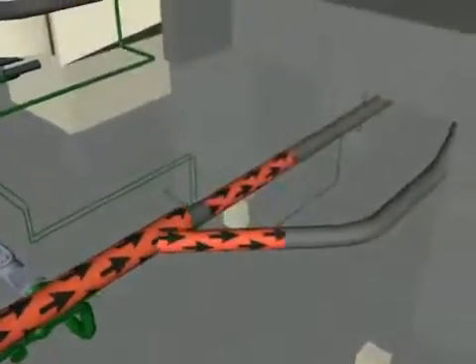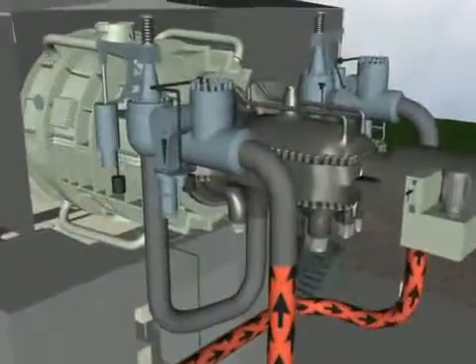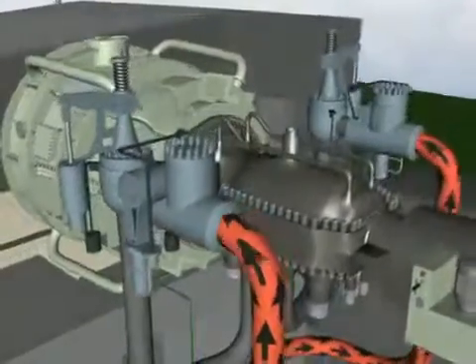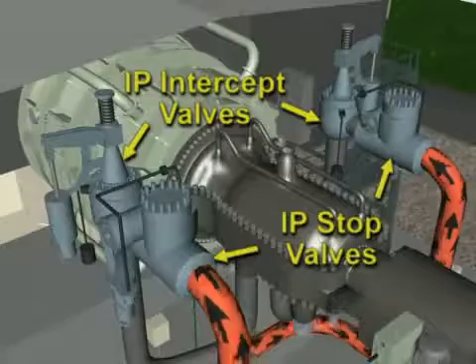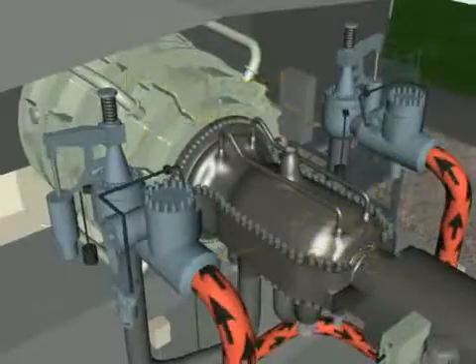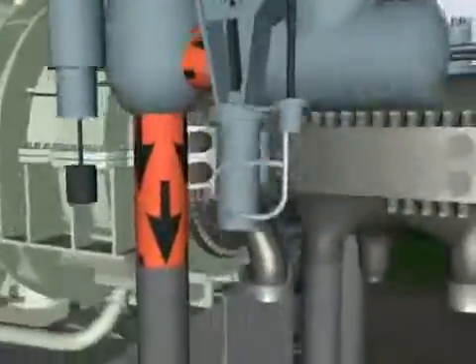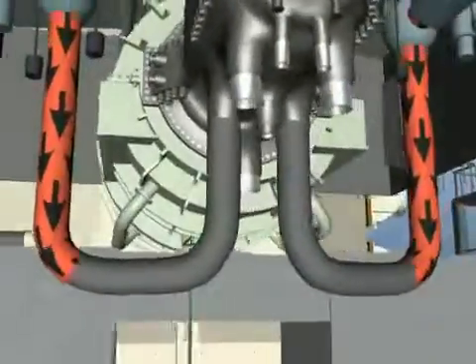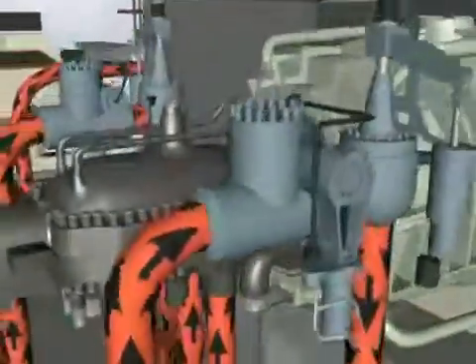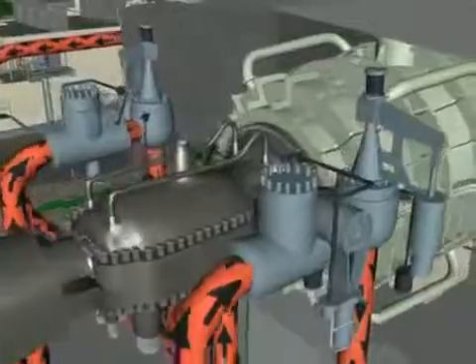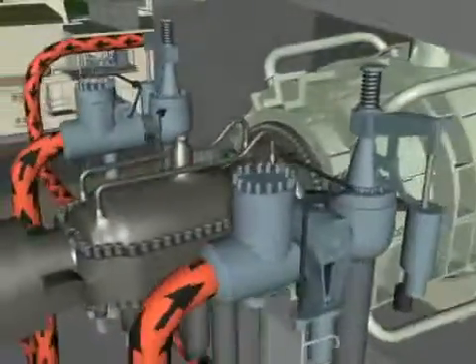The reheat steam piping splits to go to two sets of valves, one set on each side of the steam turbine. Each reheat steam valve set consists of a stop valve and an intercept valve. With the stop and intercept valves open, steam flows into the two reheat steam inlets on the bottom of the steam turbine casing. In the event of a turbine trip, the reheat stop and intercept valves will close rapidly to shut off steam flow to the reheat and LP sections of the steam turbine.